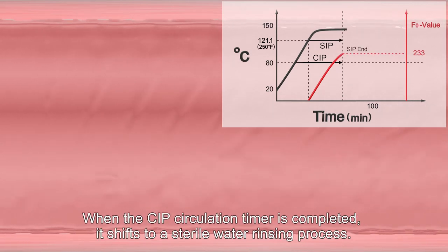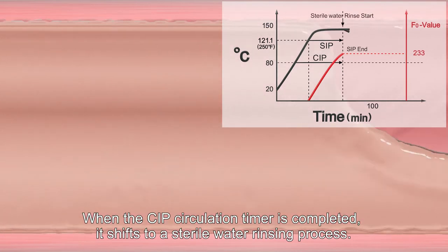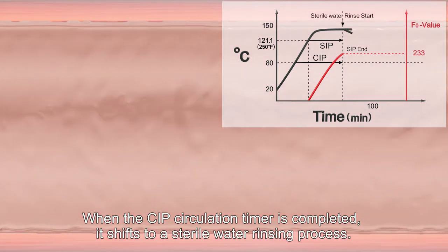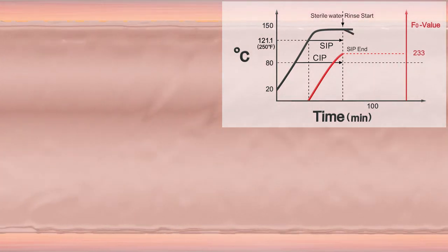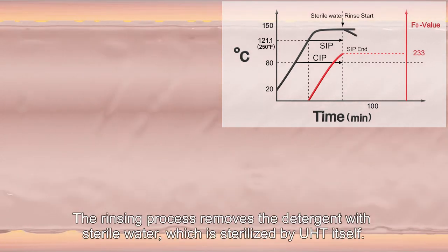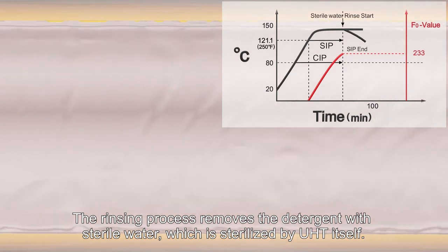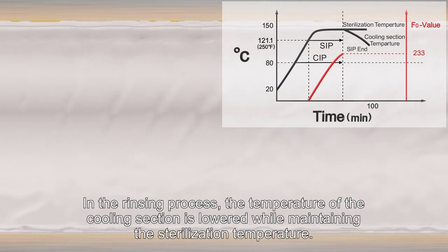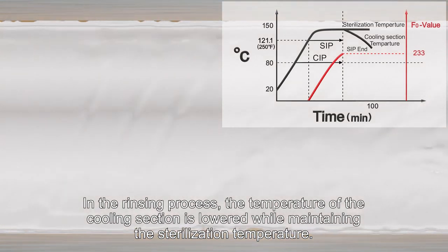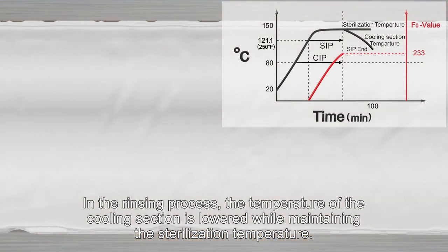When the CIP circulation timer is completed, it shifts to a sterile water rinsing process. The rinsing process removes the detergent with sterile water, which is sterilized by UHT itself. In the rinsing process, the temperature of the cooling section is lowered while maintaining the sterilization temperature.